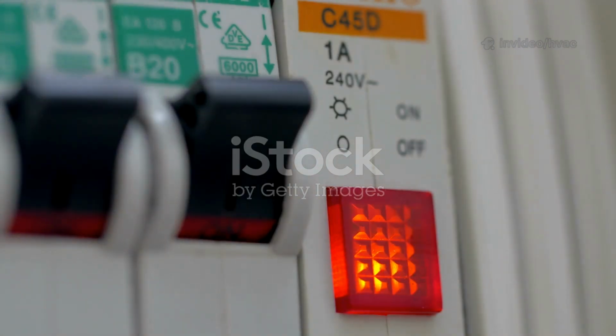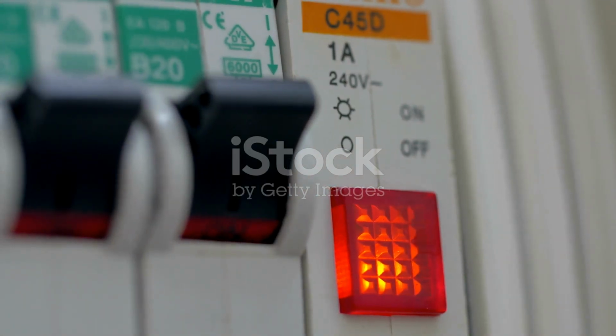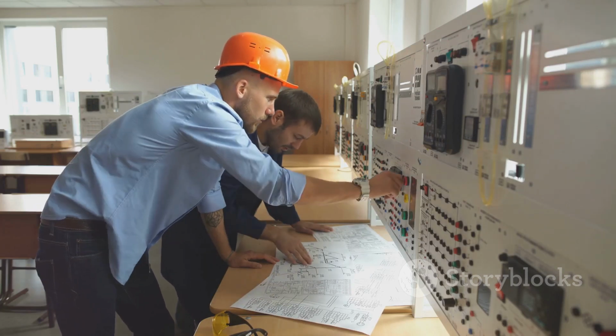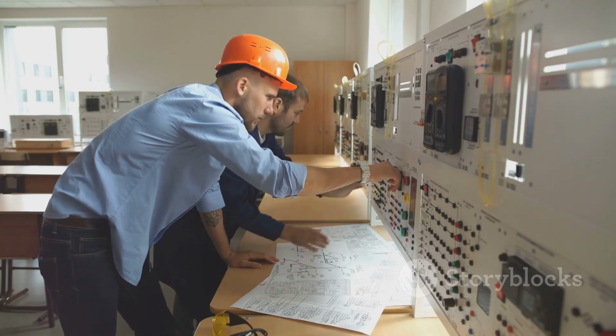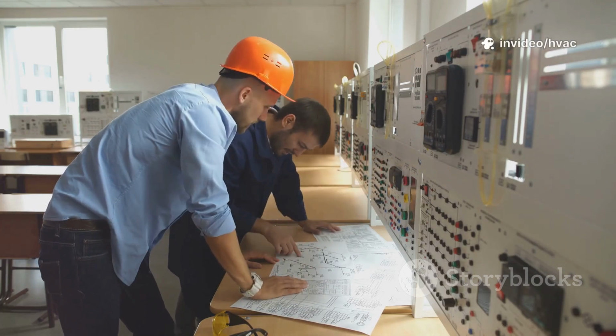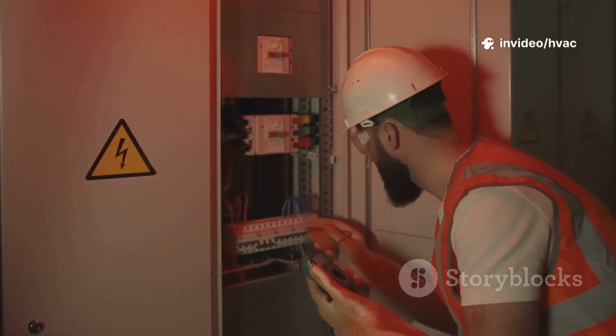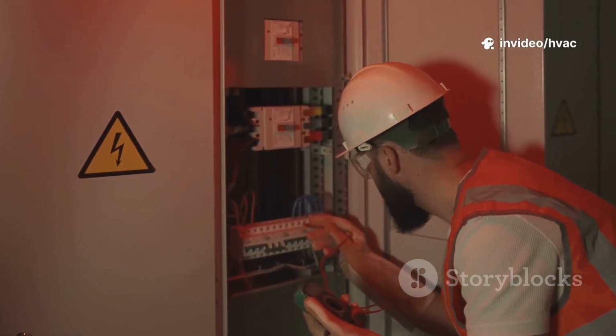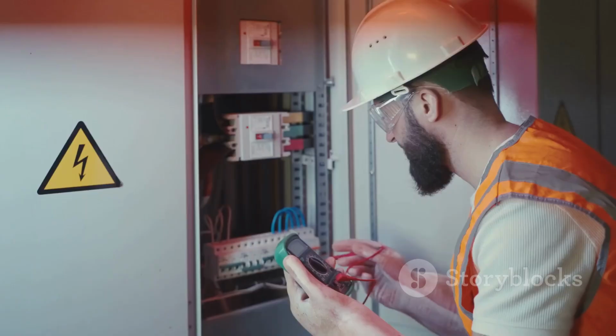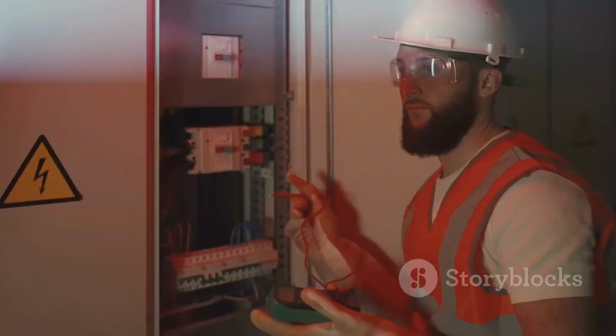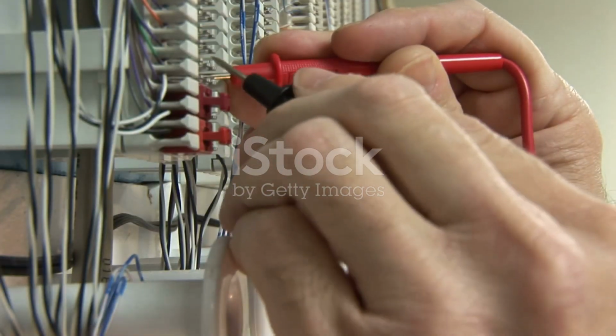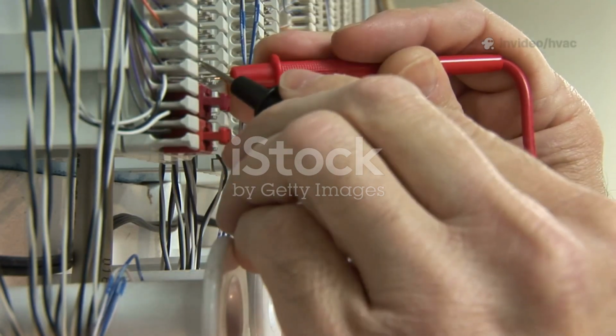Let's break down the language of relays: normally open, NO, and normally closed, NC, and see how they keep HVAC systems safe. We'll also dive into condenser water cooling tower safety interlocks and AHU high static, low static, and fire damper interlocks, so you know exactly when to use NC and NO contacts in your designs. NO contacts are open at rest. Electricity can't flow until the relay is actuated.